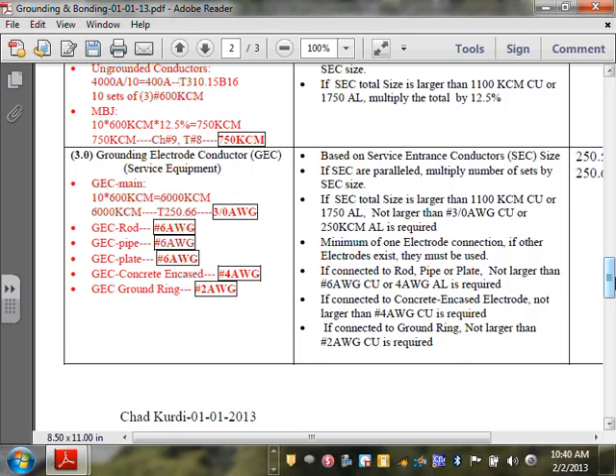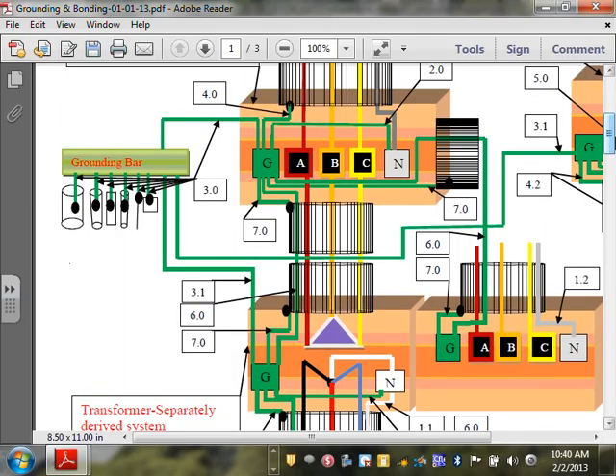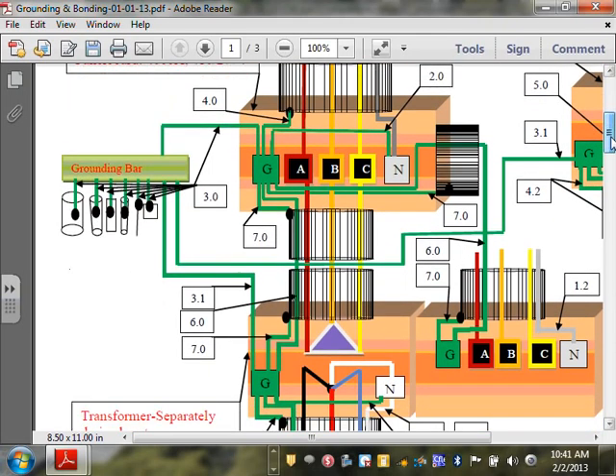My judgment, if you're building a concrete building or metal building and you have foundation in the ground, and you tie to all these foundations and you go with 3 aught in multiple locations, you're good enough. But honestly, I would not depend on 3 aught. Grab all these and bring them with 3 aught to your service? I wouldn't go there. I would go higher, coming from this point into here, probably, in this case, 350 or even 500 kcm just to the switchgear, because that's a very major part of your grounding electrode system. Okay, so that's kind of the runaround answer for that one.